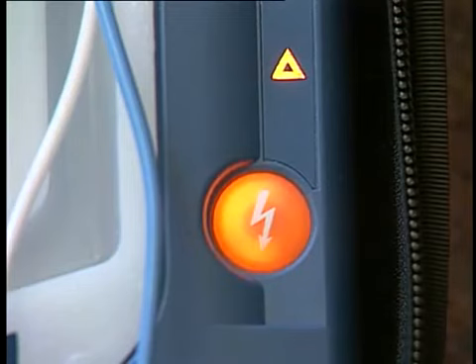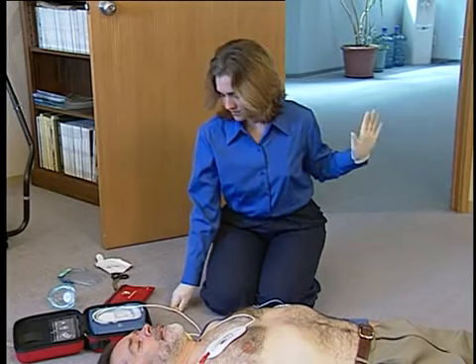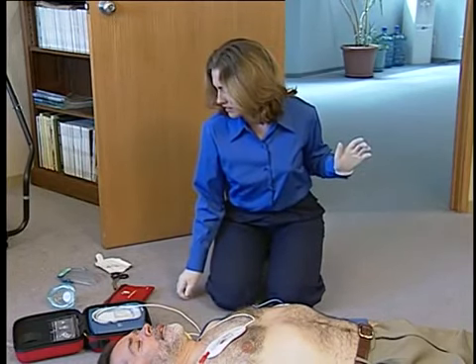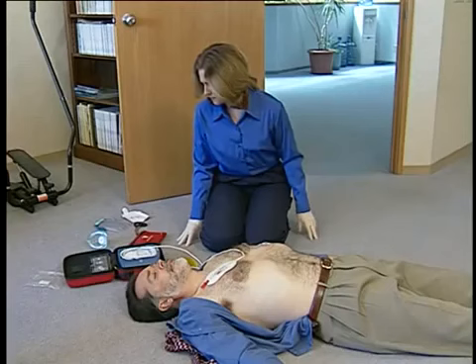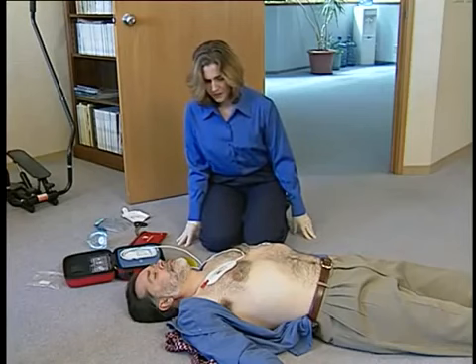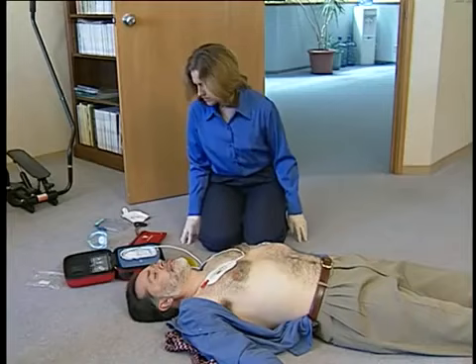Rescuers should not touch the patient while the defibrillator is analyzing. The triangular caution light will turn on and start flashing as a reminder. The OnSite will tell you if a shock is advised. If a shock is advised, the caution light will stop flashing and remain on, and the orange shock button will start flashing. Before pressing the button, you must make certain that everyone is clear of the patient. Check visually that no one is touching the patient and instruct everyone to stay clear. Press the orange shock button to deliver the shock.